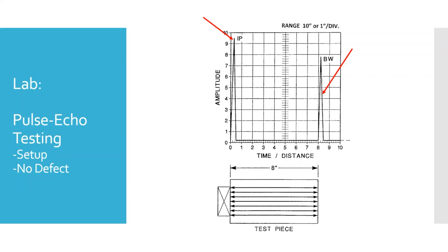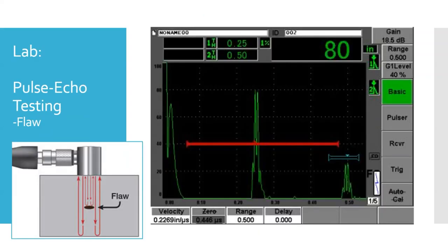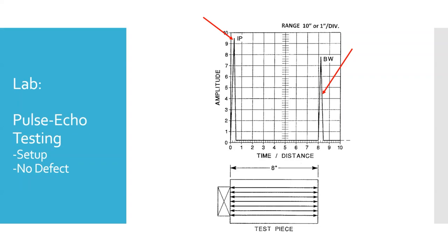Those speed of sound tables are a starting point. They'll say, okay, for this material, it's 0.3572 inches per microsecond. That's your starting point. Then we need to calibrate, because maybe today in this given material, instead of 0.3572 inches per microsecond, it's actually 0.3570 inches per microsecond, or maybe it's 0.3578 inches per microsecond, depending on the temperature. That's what we're going to be adjusting to get an accurate distance. We have to have a known distance to compare our output against and adjust the speed of sound to match what it is exactly at that moment in time.